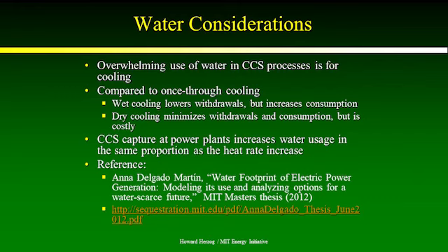You can put wet cooling towers in, and this will really lower the withdrawal rates. And in many areas, like for power plants now, do require cooling, but this will also increase water consumption. Dry cooling really minimizes, can almost eliminate both the withdrawals and consumption of water, but that's also very, very expensive.